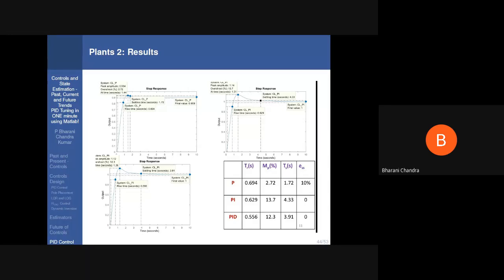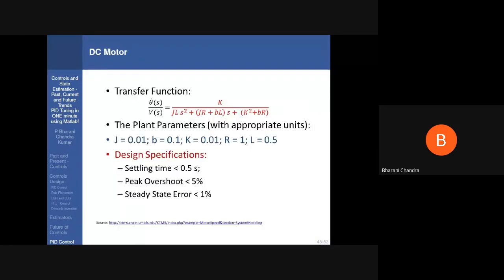However, if your plant or control needs some KP, KI, KD values, then the one method I'm going to show here will work in 90 to 95% of cases. It doesn't need a complex heuristic optimization algorithm. By using the standard one minute method, you can tune it.